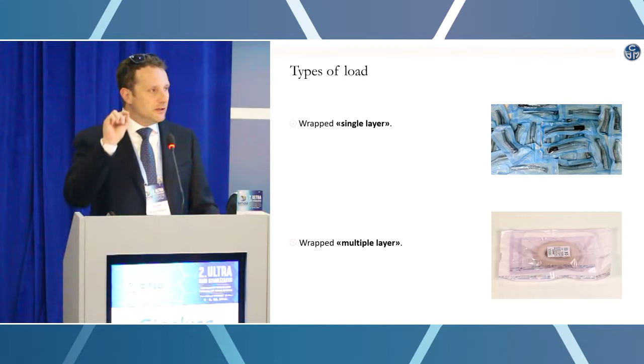On the other hand, a simple hollow item is what is simple hollow: a cup, a basin, something that has a very big hole, but it's very short. Why am I stressing this definition? Because from our point of view as manufacturer of benchtop sterilizers, we have to give you a table where we guide you on the selection of the proper cycle you have to use to sterilize every single different item.